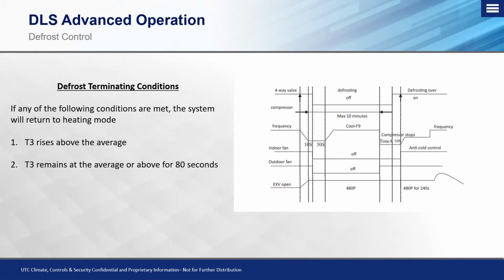Okay, so those are going to be the factors that start and stop a defrost cycle, namely being an importance on the T3 or the outdoor coil temperature sensor as being one of the factors that initiates and also being the factor that ends a defrost cycle. The defrost cycle will not continue longer than 10 minutes maximum, and then it will naturally take itself out. Of course, if that T3 sensor is still below that average, then it will initiate itself into another defrost cycle. And sometimes, depending on your geographical location or your weather conditions, it does take multiple cycles to clear that coil off. It does happen.